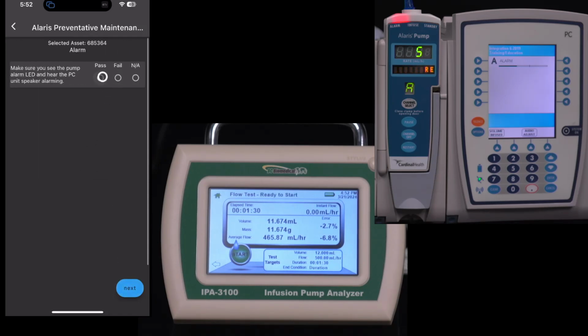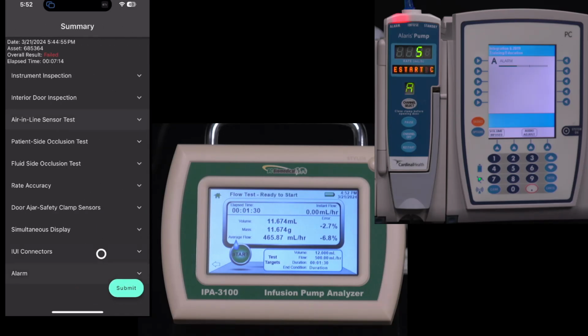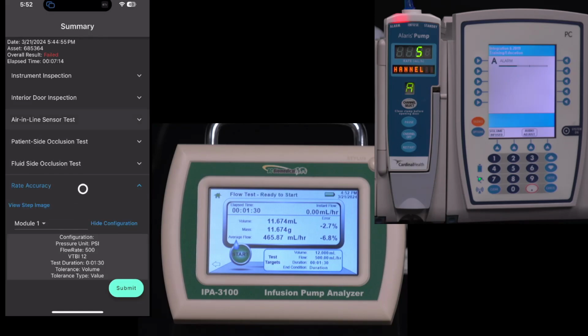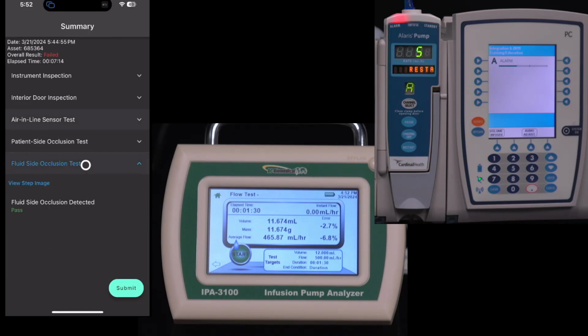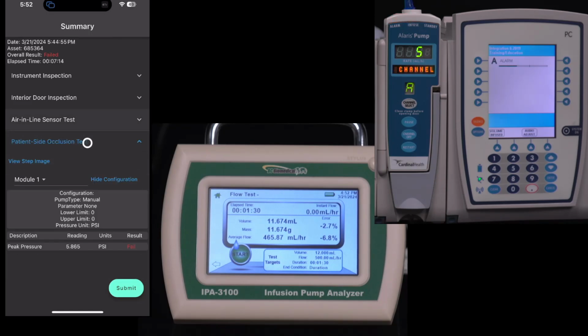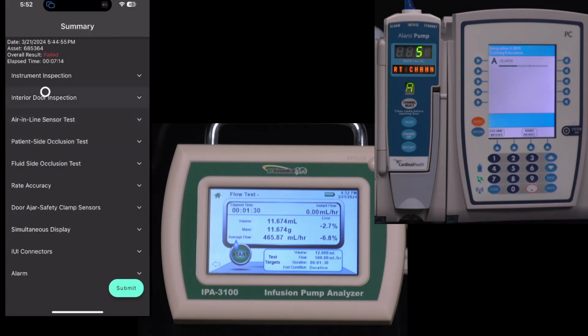And see the pump alarm, we definitely saw the alarm and we heard the alarm. We tested all the keys. Now, the auto sequence is complete. So I can look at all of the test data. There's my rate test, occlusion test. Here's the one that failed. So this shows me that the overall test result was fail.